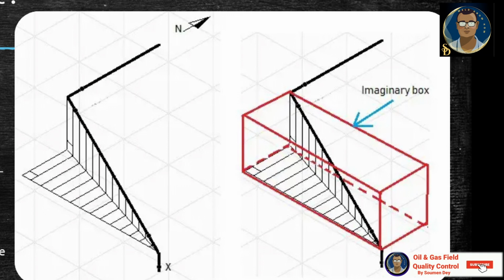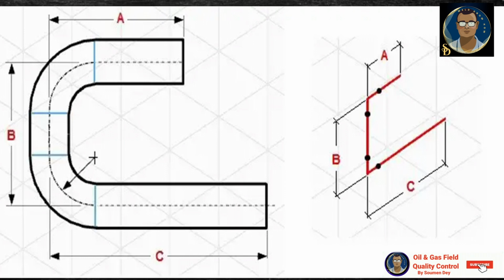A north arrow is provided in all piping isometrics to inform the location of the piping system in the piping or general arrangement drawing. Piping dimensions in isometric. How to put dimensions in isometric? The piping isometric also has coordinates and elevation detailed information to verify the exact length of the pipe in horizontal and vertical axis respectively. The dimensions in isometric drawing are measured from the pipe center line and not from the outer diameter of the pipe. Refer to the image attached below for reference.